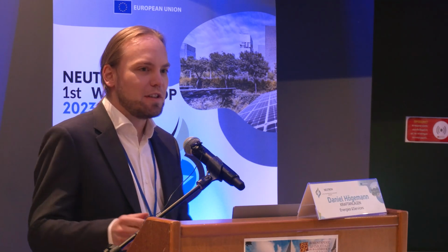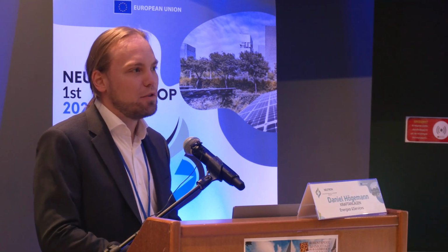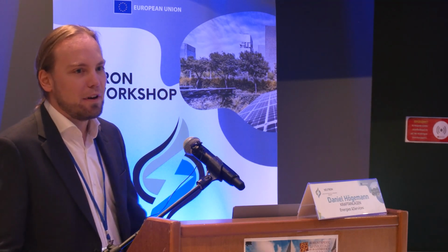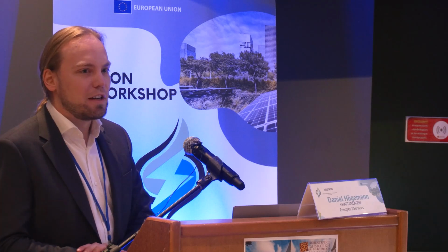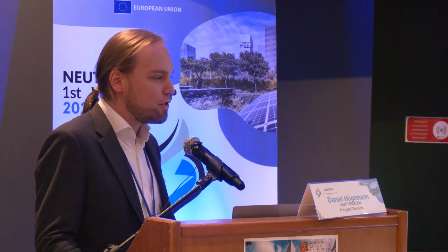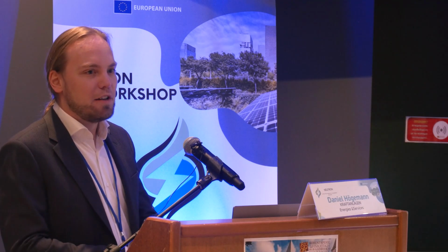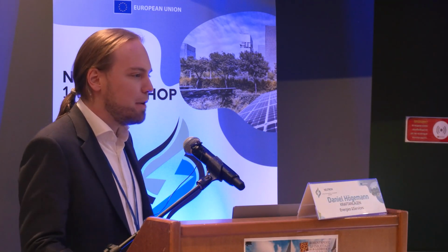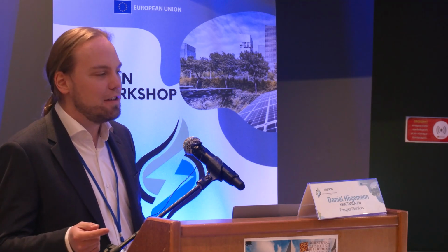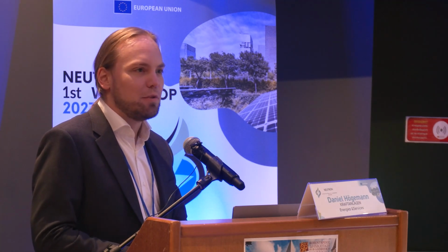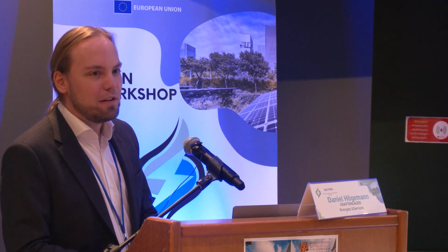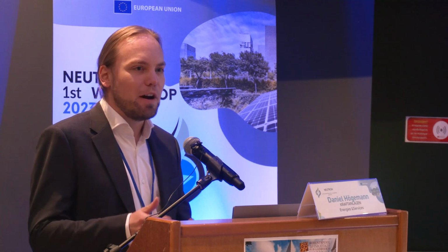By doing so, we can drastically reduce the cost of the energy storage, because storing thermal energy is way cheaper than storing electric energy. And then afterwards, when we need it again, we can use the stored high temperature thermal energy to run a thermodynamic cycle, for example, a combined heat and power steam turbine cycle, converting it back to electricity when solar and wind are not available, and as a side effect, providing the heat from the cycle to, for example, district heating networks. And by this, we are in principle able to replace the fossil fuels in a combined heat and power application.